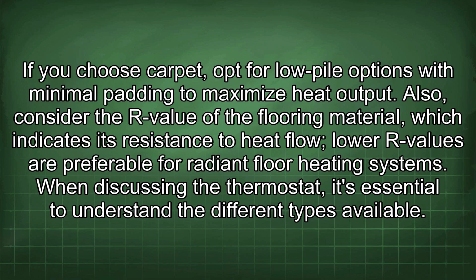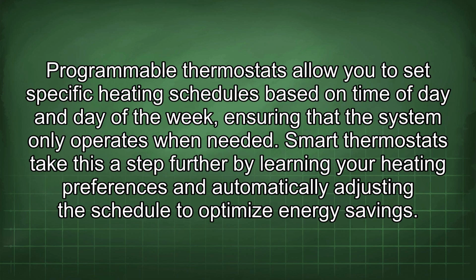Also, consider the R value of the flooring material, which indicates its resistance to heat flow. Lower R values are preferable for radiant floor heating systems. When discussing the thermostat, it's essential to understand the different types available. Programmable thermostats allow you to set specific heating schedules based on time of day and day of the week, ensuring that the system only operates when needed.